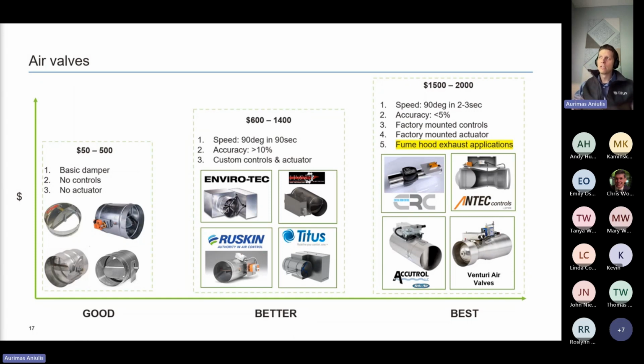The reason for that packaged solution is so that we can maintain the specs listed above, the actuation speed and the accuracy. The primary differentiator for any critical environment air valve is its ability to do fume hood exhaust. Fume hood exhaust can have lethal corrosive chemicals that can kill you within 24 to 48 hours, and I'm not making this up. So it's important that the device is reliable and can withstand those environments through the life of the building. Right now I have customers asking me, can your valve survive 20, 30 years, which is the life of the building? With a Venturi air valve, I'm comfortable to say yes, but there are some serviceable items like the actuator on the valve. So regular maintenance will allow you to have an airflow valve for the duration of the building.